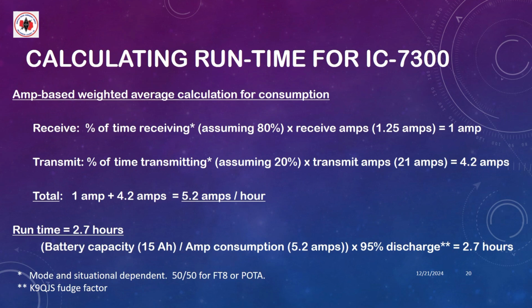And this is an amp-based weighted average calculation for consumption. While receiving, the transmitter needs 1.25 amps. And for this particular example, I'm going to assume receiving 80% of the time. At 1.25 amps, that means that the average is 1 amp. Transmit is the balance of that time. 21 amps is required. So the total amperage on average shown there is 5.2 amps per hour.